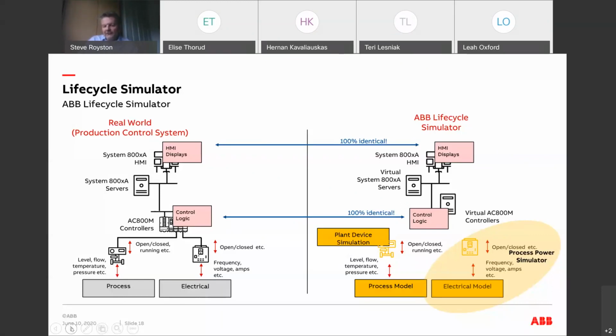We can run that against the process model, and also run the simulation against an electrical model with the process power simulator, so that we can not only emulate what happens in the process and the feedback coming from the valves and motors - the open and closed feedbacks - but also simulate the frequency, voltage, and currents in the power distribution network, and the responses we'd get back from the protection relays regarding whether a circuit breaker is open or closed, or whether a generator is running or not.